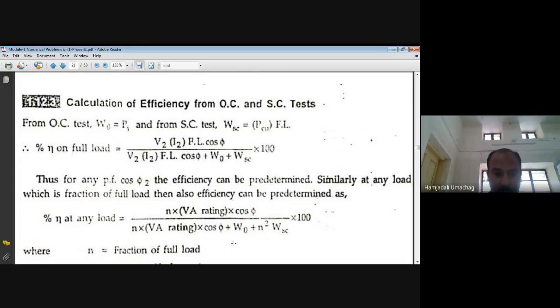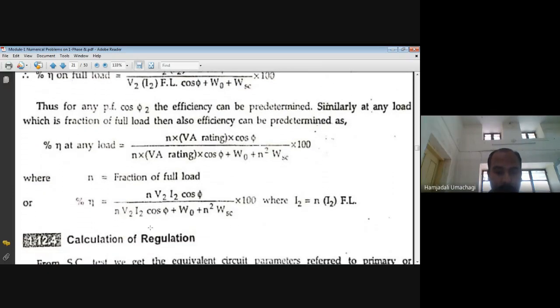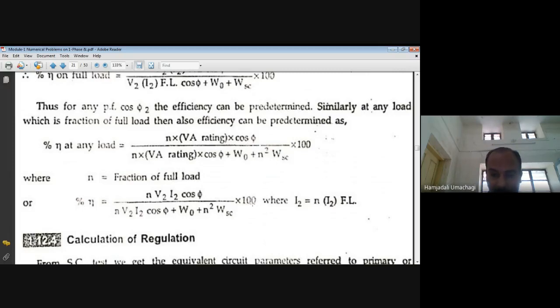The percentage efficiency η(n) equals n·V₂·I₂·cos φ divided by (n·V₂·I₂·cos φ + W₀ + n²·WSC) into 100, where I₂ = n × full load current I₂FL. This formula applies for any loading condition and any given power factor.